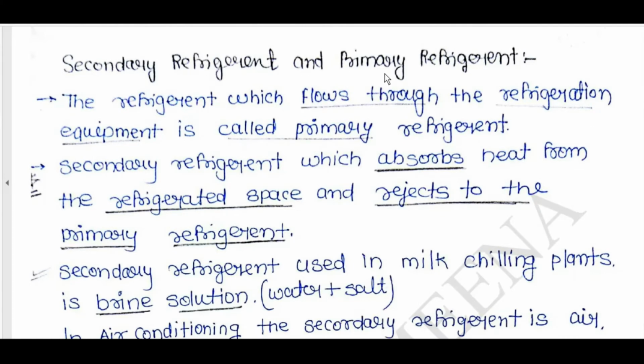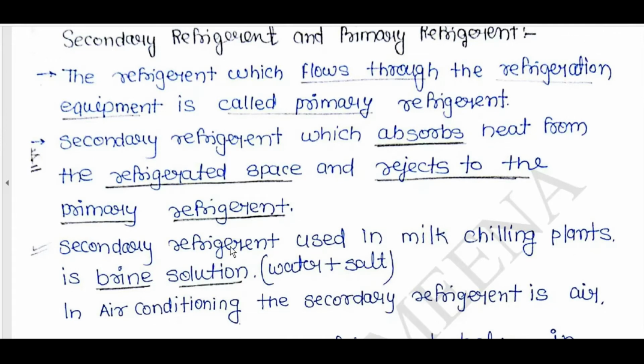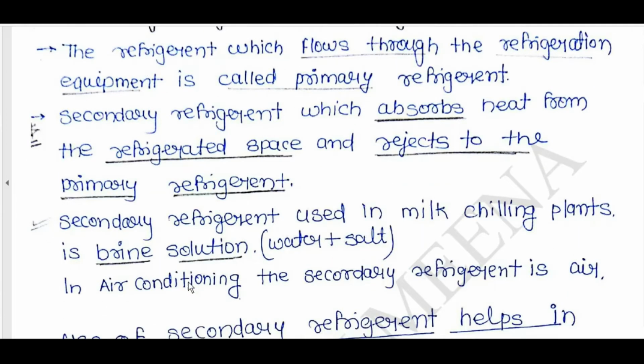Secondary refrigerant and primary refrigerant. The refrigerant which flows through refrigeration equipment is called primary refrigerant. The secondary refrigerant absorbs heat from the refrigerated space and rejects it to the primary refrigerant. Secondary refrigerant used in a milk chilling plant is brine solution. In air conditioning, the secondary refrigerant is air.